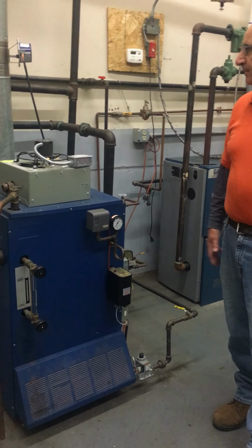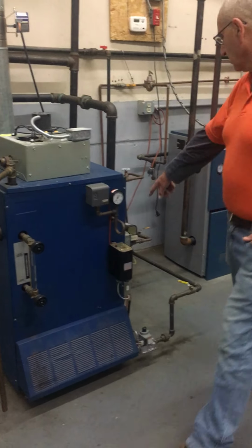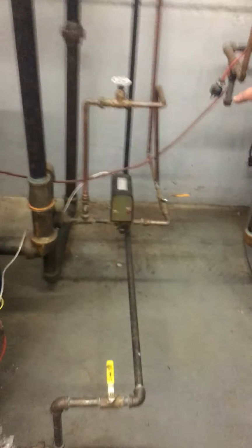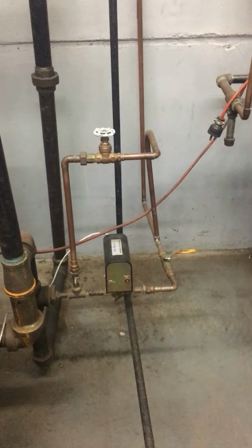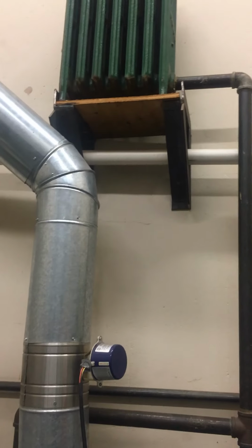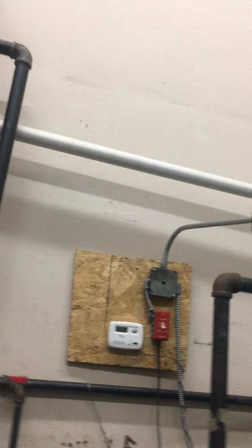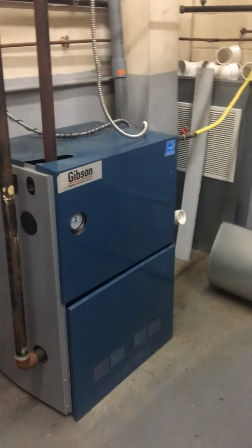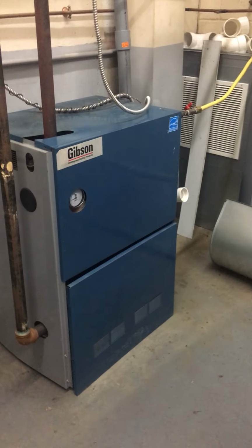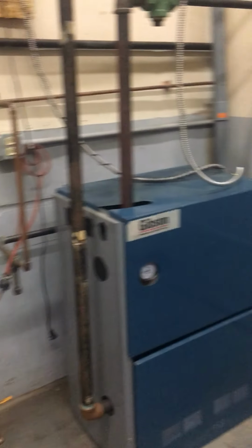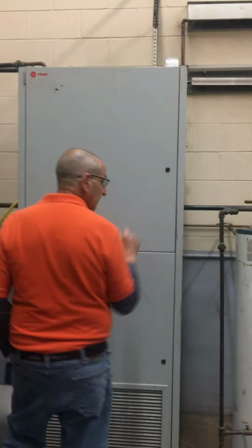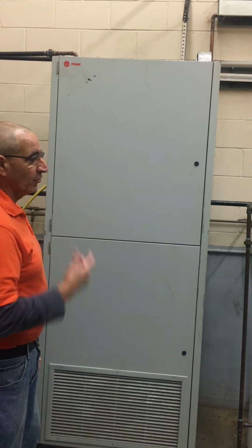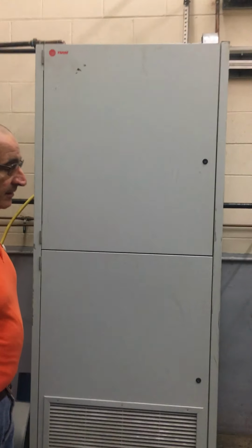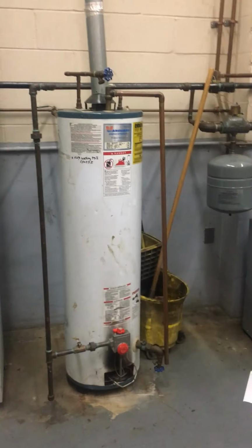gas-fired steam boiler done with a Hartford loop and everything. You can see the Hartford loop here, an automatic feeder. The motor has a damper on it, and we have a radiator to use as our heat sink for the heat, which you would have in the steam system. Then we have a high efficiency hydronic boiler here, which is a 94%. We also take the heat out of here and we dump it into this heat sink, which has a water coil in it for heating. And once it gets up to a certain temp, the blower kicks on and it blows heat in here as well.